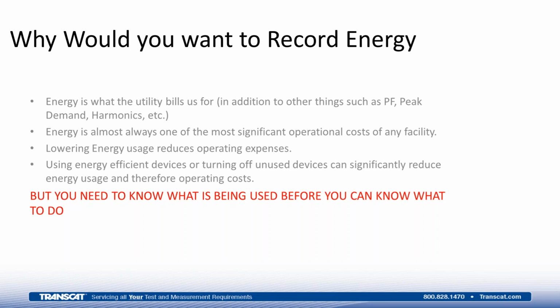to, for instance, one of the things utilities can bill for is peak demand. And if you turn on all your equipment in the morning when you're in the peak period, you will necessarily see an additional charge. If you could stagger your startup, in a lot of cases, you can actually save some energy. The key thing to draw from all this, though, is you need to know what you're using in order to know what you could curtail to lower your energy cost.